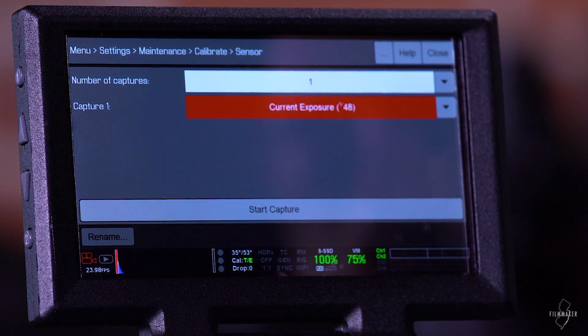And then you'll hit Start Capture. I'm not gonna hit start because it's gonna run through something we don't need to see, but what you'll wanna do is actually make sure all the light is being blocked by locking the lens cap into place. I recommend performing this without a lens on and just using the lens cap. You can also drop like a dark cloth or a duvetyne over the camera if you wanna be super duper safe to make sure no light's getting in.